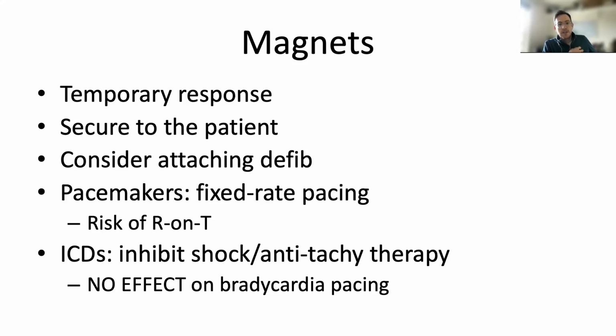They make the quite pragmatic point that you need to make sure that the magnet is firmly secured over the device to the patient, i.e. taped on, because obviously it's only working as long as it's there. And they do warn that application of the magnet might cause the device to emit quite a loud auditory alarm, but that's nothing to worry about and to be expected. As I say, if you're using a magnet, consider having pads on.